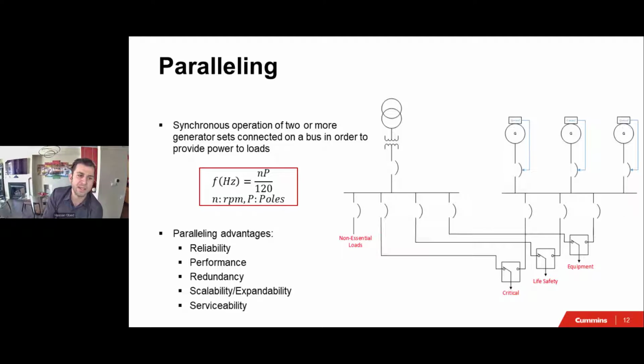So paralleling is a synchronous operation of 2 or more generator sets connected together. Synchronous operation because we can correlate that sinusoidal wave, the output from the genset, to the position of where the rotor is inside that stator. And we can also correlate that frequency, for example, 60 hertz, to the number of poles and the number of rotations. Typically, all the alternators that you'll be dealing with specifying are 4-pole generators. And so for 60 hertz, the RPM would be 1800 RPM. This is for 60 hertz applications in North America.